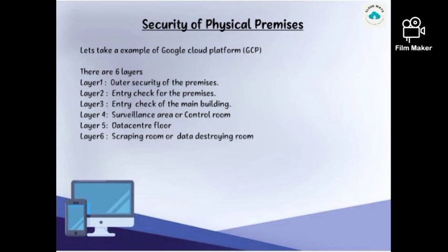Layer 6. In Layer 6, the disks are erased and destroyed and a very small number of people are allowed to enter. Drives that need to be retired from the data center come to this room through a secure two-way locker system, which means that only assigned technicians can pull the drives from the lockers to either erase or destroy them. Before destroying them, they are scanned and then transported to the crusher room. Here the hard drives are totally crushed. At the end, when anyone is leaving the data center, they have to go through a full body metal detection each time they leave the data center floor.